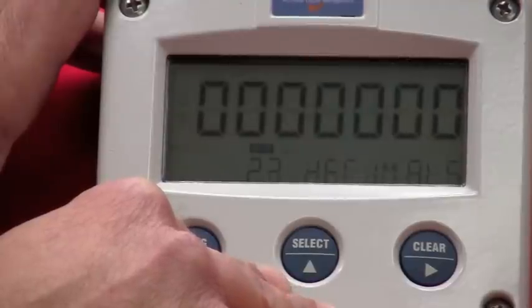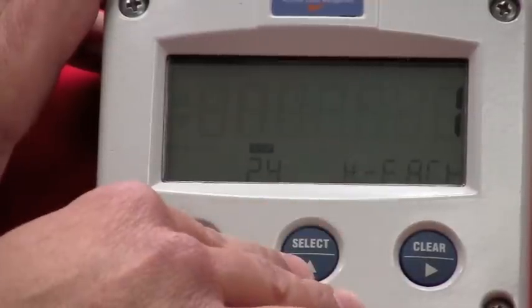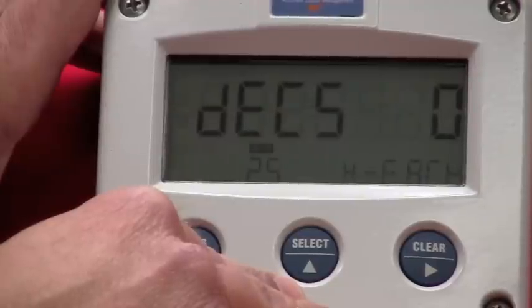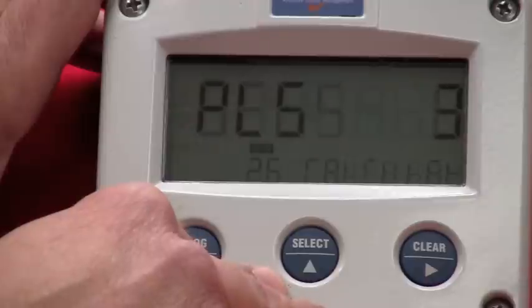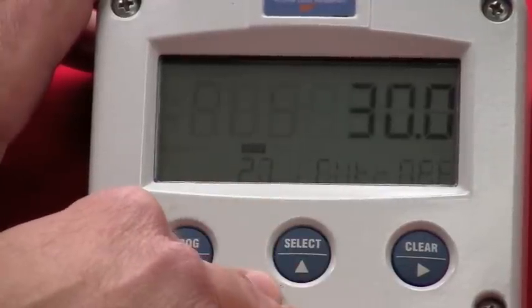Next would be your decimal point for your flow rate. Your K factor for your flow rate. Again, this is set at 1 for your demo. That way, every click registers as a pulse. Decimal point for your K factor. Calculate. Now, this is basically a filtering option that you have available with the unit. Ours is set for 3. I'll leave it that way.